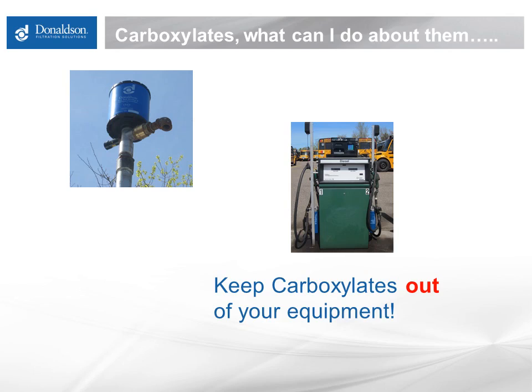While many of the fuel-insoluble carboxylates are formed upstream of end user tanks, not all of them are. If you have a common high pH tank bottom water environment in your tank, these carboxylates can certainly form in there as well. Proper tank maintenance and a good breather filter will help minimize the risk of these carboxylates forming in your tank. Filtering the fuel at the outlet of the tank will prevent these contaminants from reaching your equipment. These filters will plug up if insoluble carboxylates are present in the fuel, but that is better than having your equipment stopped cold.